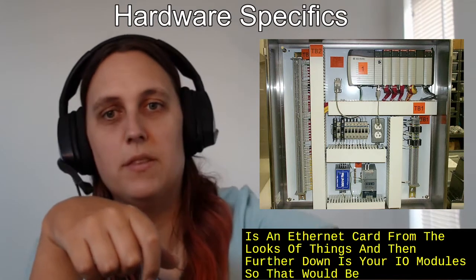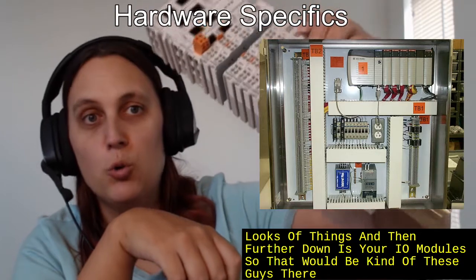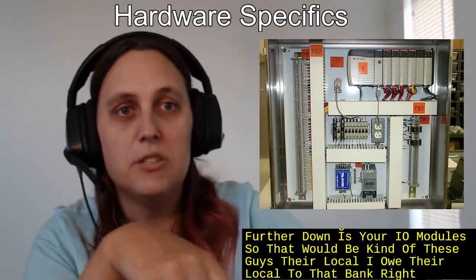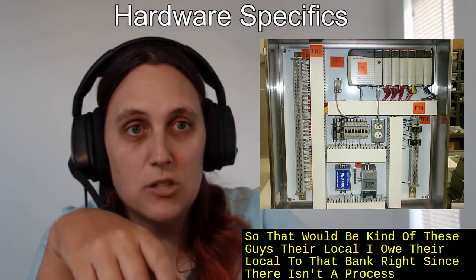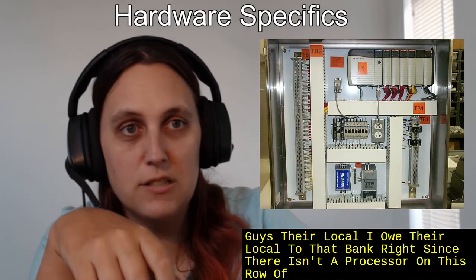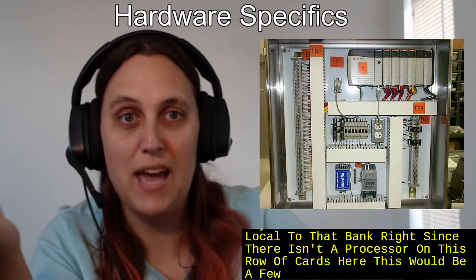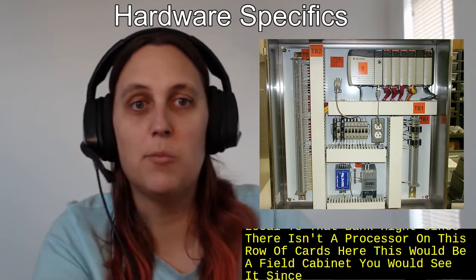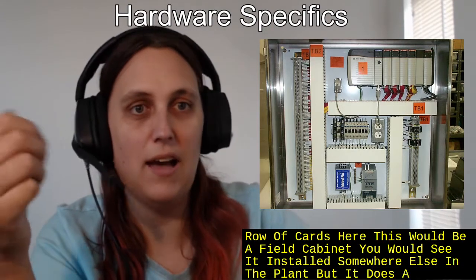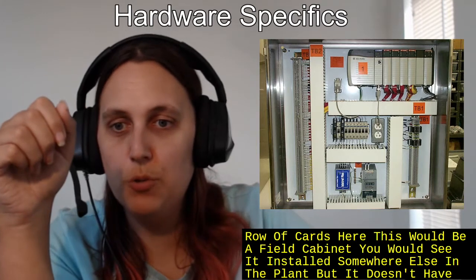So that would be these guys. They're local I/O. They're local to that bank, right? Since there isn't a processor on this row of cards here, this would be a field cabinet. You would see this installed somewhere else in the plant because it doesn't have a processor.